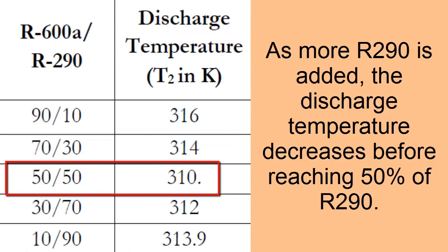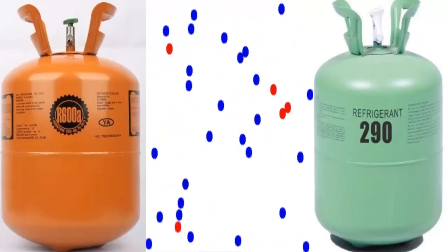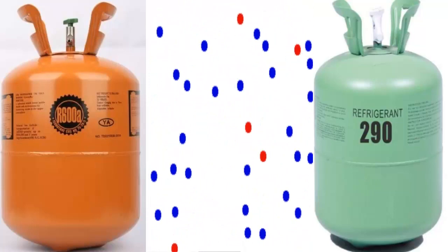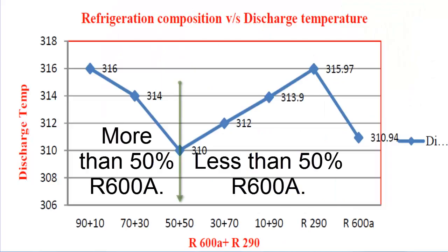The greater the amount of R290 in the mixture, without exceeding 50% concentration, the compressor discharge temperature decreases. After surpassing 50%, the opposite occurs. Remember that a lower compressor discharge temperature increases the lifespan of the motor windings. On the screen we have different discharge temperature values for some mixtures between R600A and R290.